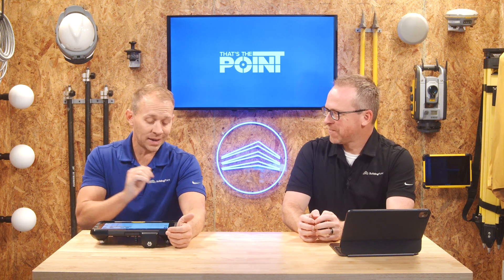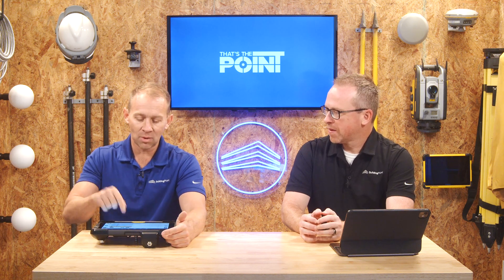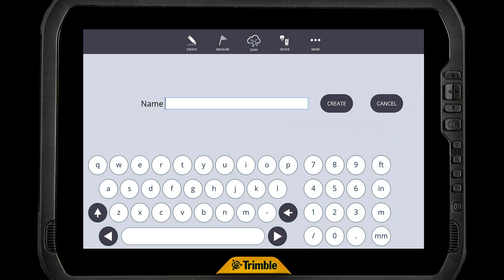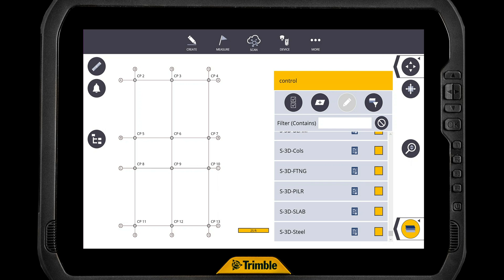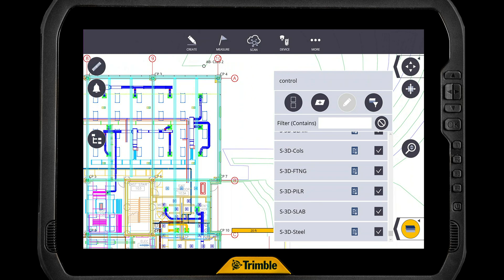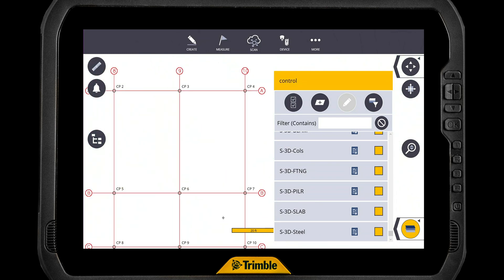You can save this so that you can quickly come back to it. When you come back the next day, you don't have to turn things on and off again. If we look at the top right of the list, there's a little funnel with a plus. If I tap on that, I can save this layer view and give it a name — I'm going to call it 'control' since this is what I would use for setting up my control. Now at the top of my layers, I have a 'control' view that can be turned on and off on its own. That's persistent — you can do any other selection with the layers you want, but you'll always have that option to go back to it. So if I turn everything else on and go to work laying out light fixtures, the next day when I want to set up again, I just turn all that off, turn on my control, and boom — there's my control. That's extremely powerful.